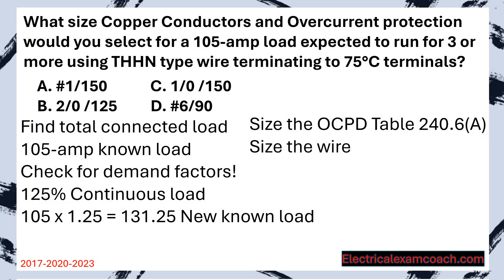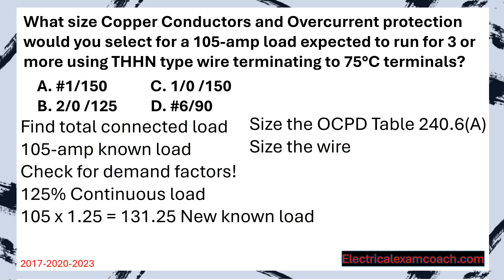Now we come back and size the wire. We head to our ampacity table on the copper side in the 75 degrees C column. We go down and find a wire that covers the known load, and we select a 1-aught on a 150 amp breaker.